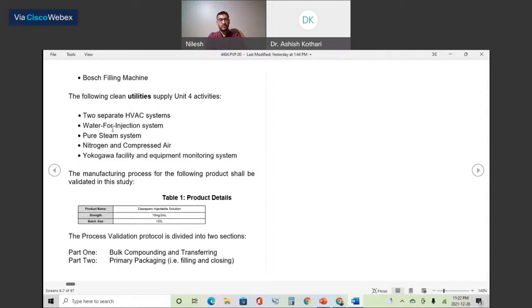HVAC system provides the differential pressure. For example, if you've seen a GMP environment, there are always 3 rooms: first is the gowning room, another is the secondary room, and the third is the primary room. The primary room is where you manufacture, compound, and compress your product, so that room has to have negative pressure. Then the secondary room, and then the change room - all 3 differential pressures should be relative to the corridor.